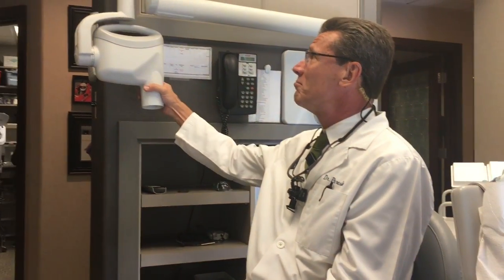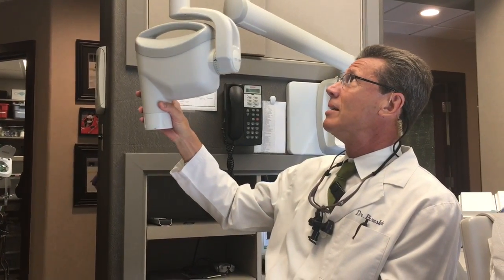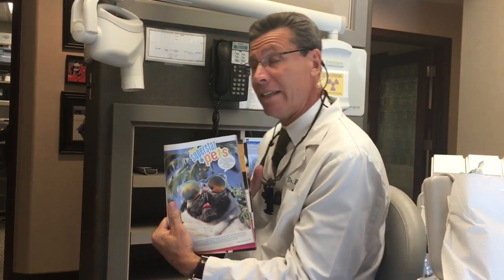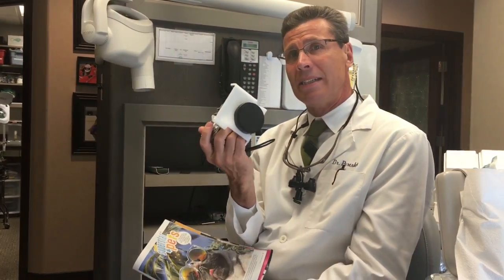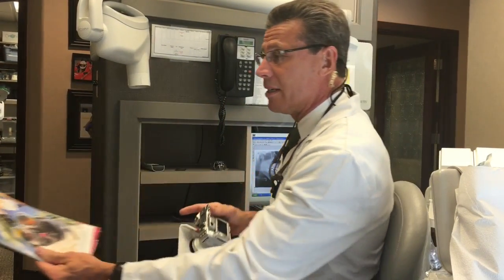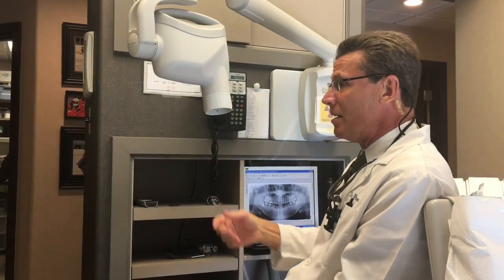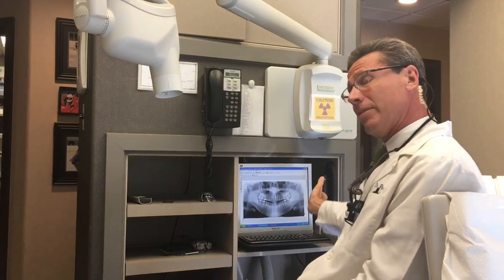X-rays come out of this tube. If you can make an analogy of a photograph — this is a photograph, this is a camera. A camera will process images using light to give you a photograph. An x-ray head like this can process images with x-ray radiation to give you a radiograph.